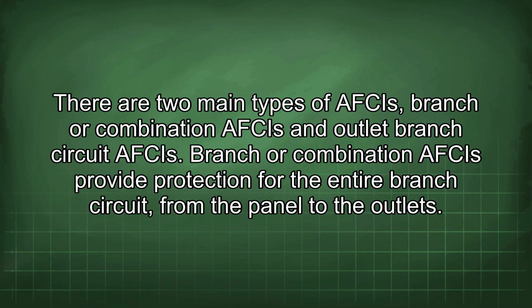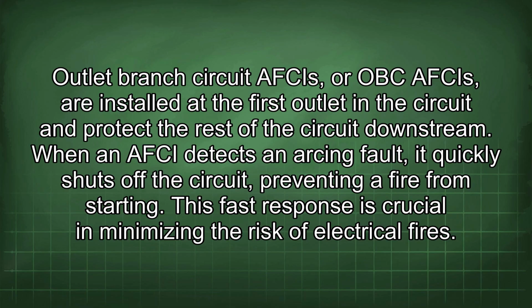There are two main types of AFCIs: branch or combination AFCI and outlet branch circuit AFCI. Branch or combination AFCIs provide protection for the entire branch circuit from the panel to the outlets. Outlet branch circuit AFCIs, or OBC AFCIs, are installed at the first outlet in the circuit and protect the rest of the circuit downstream. When an AFCI detects an arcing fault, it quickly shuts off the circuit, preventing a fire from starting. This fast response is crucial in minimizing the risk of electrical fires.